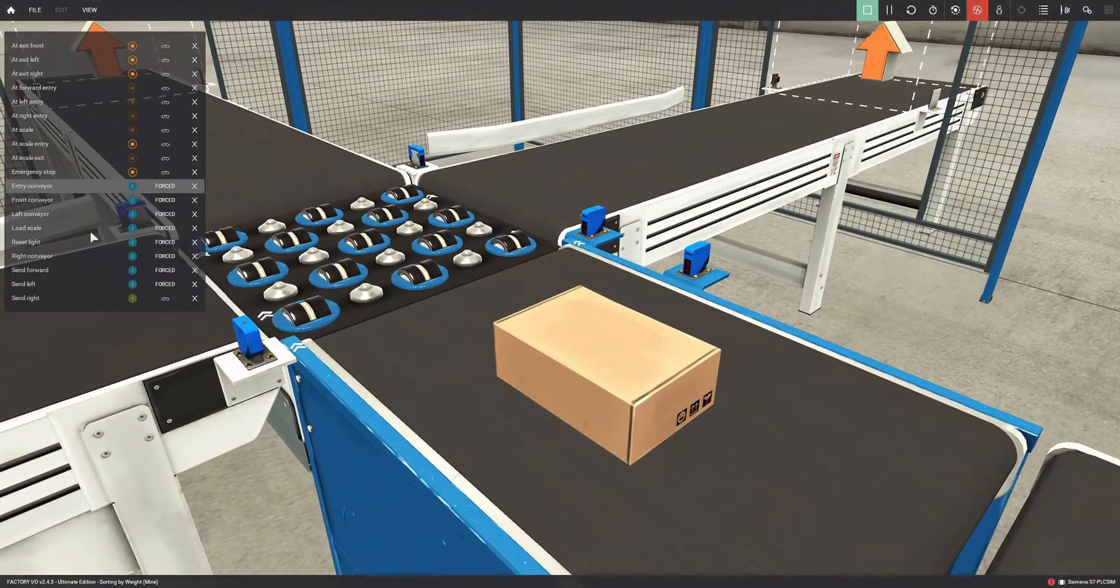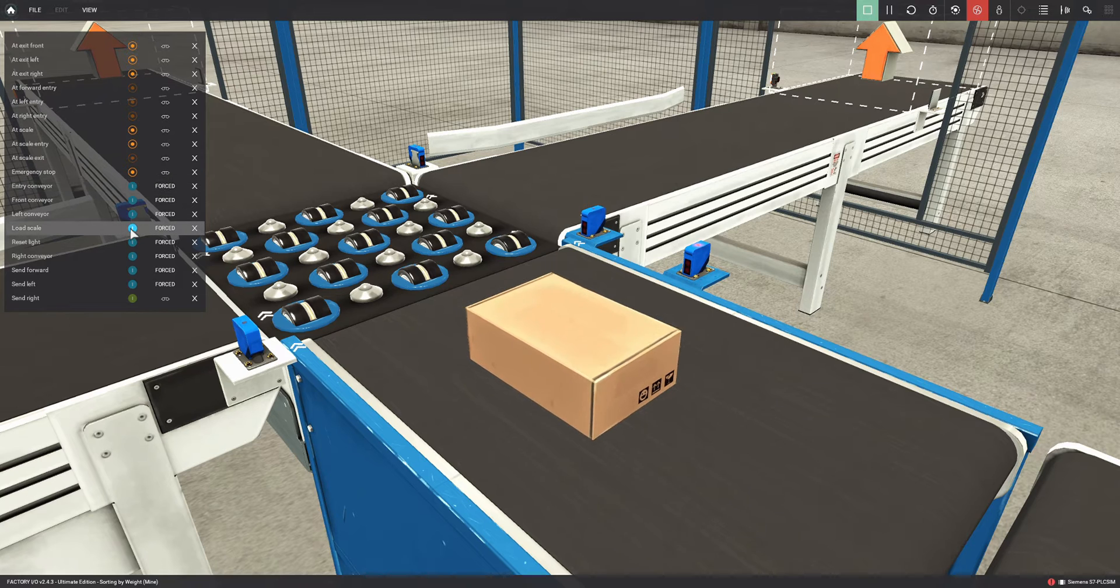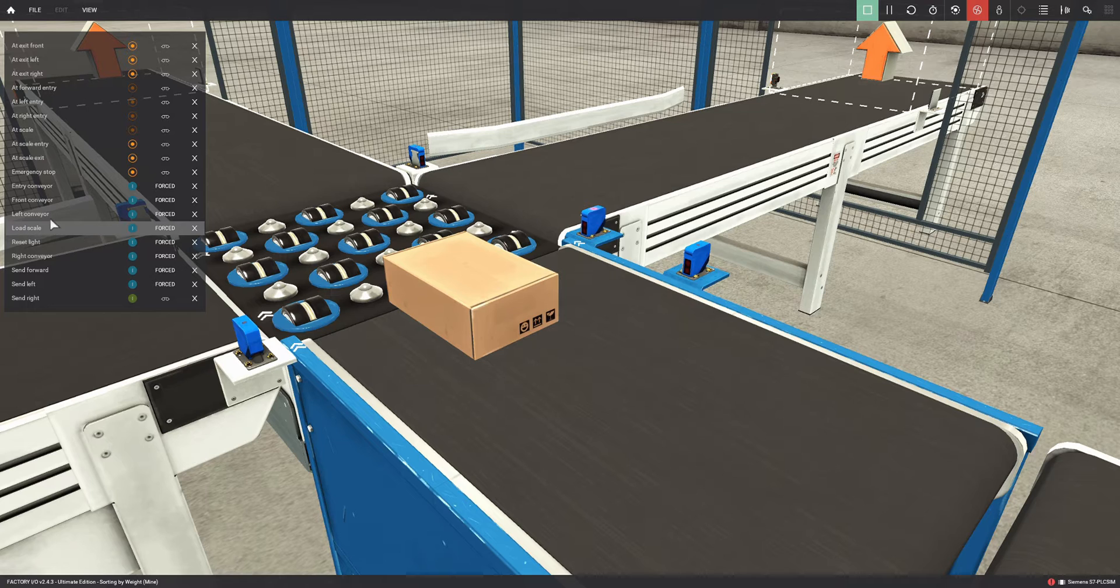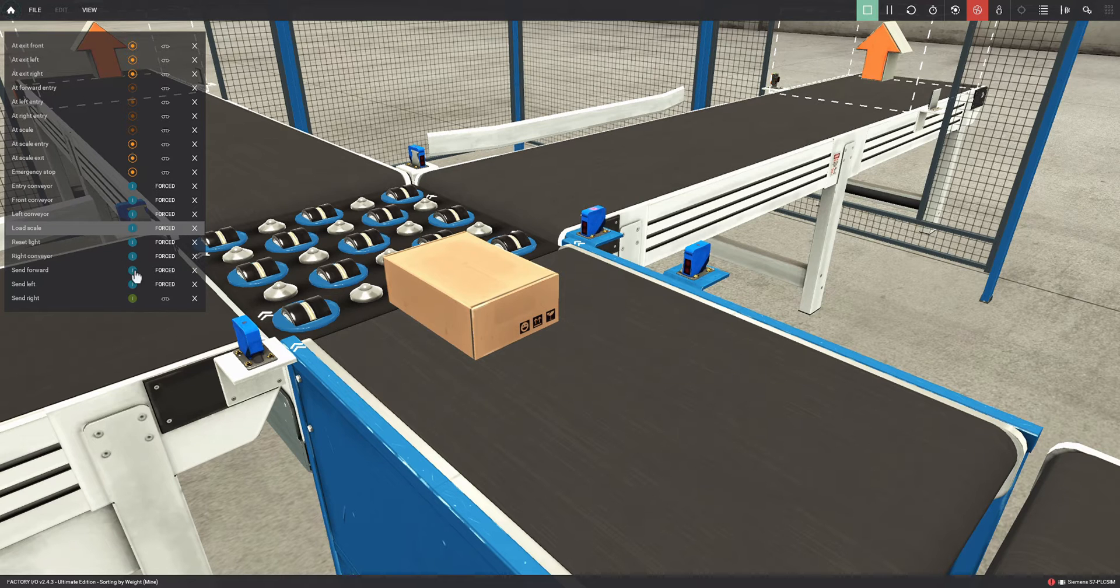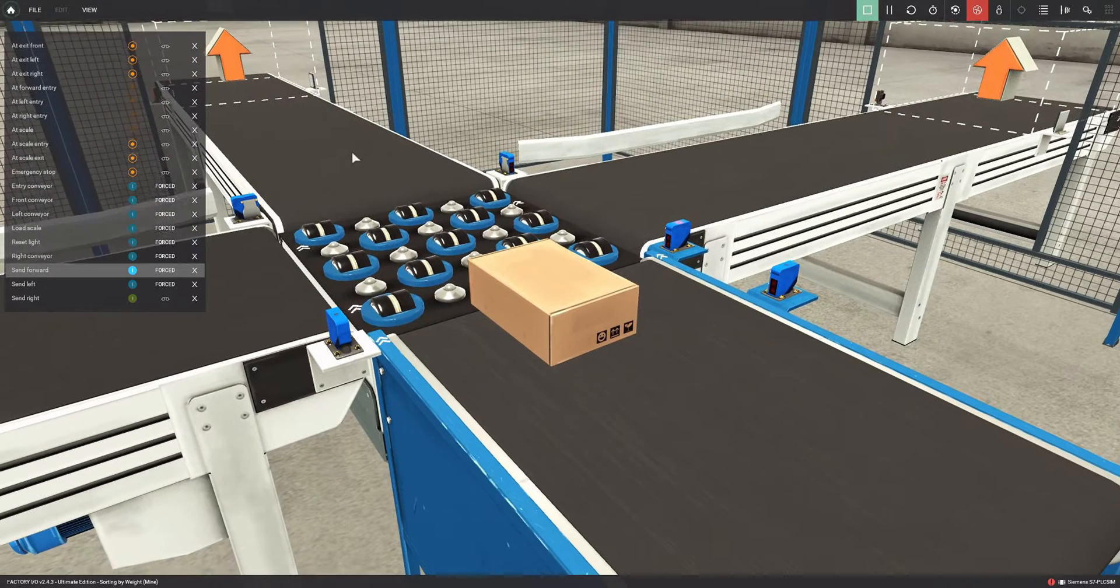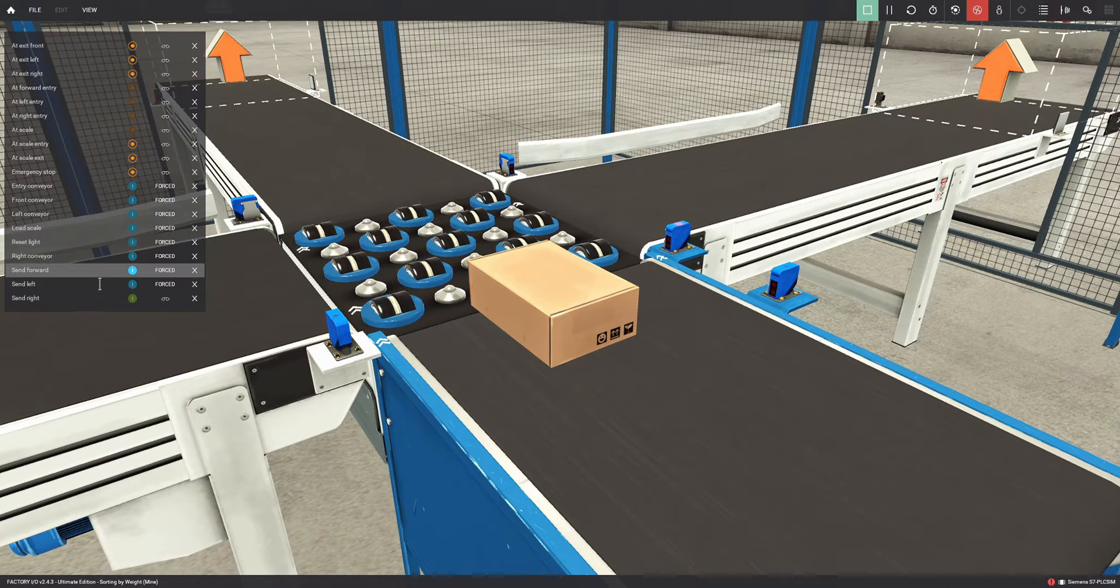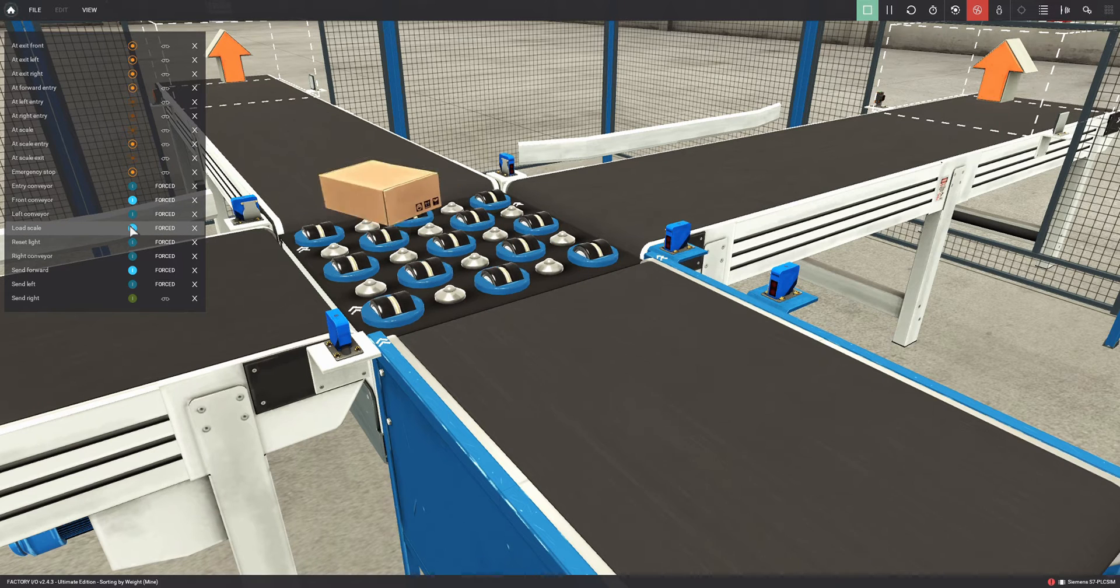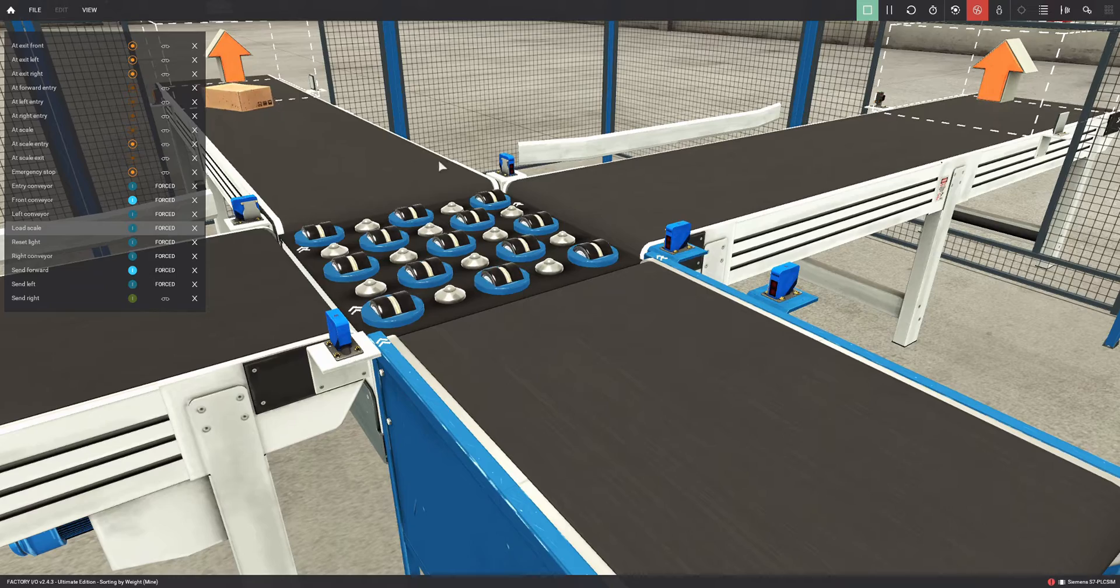What we need to do is when the box reaches this sensor here, this entry photocell, we need to make the rollers lift and rotate in that direction. At the same time, the output conveyor must activate, otherwise it's useless. The box continues until it reaches this sensor. We see the box is being detected, so we need to activate the Send Forward output. As we see, the rollers start to move. We also need to activate the output conveyor, which would be the Front Conveyor. We activate these two. The piece exits, as we've seen.